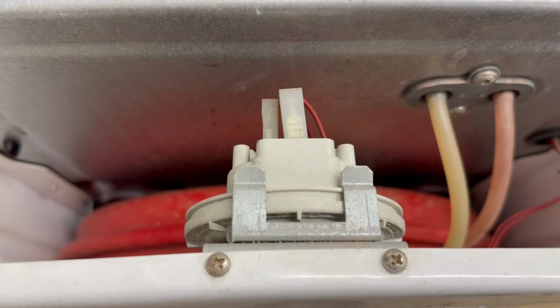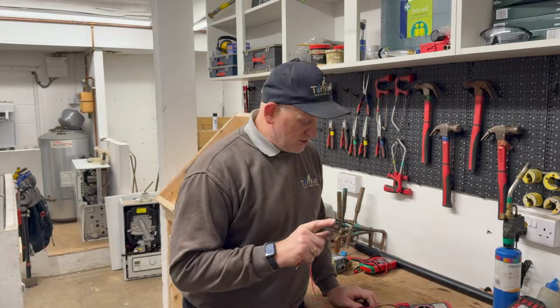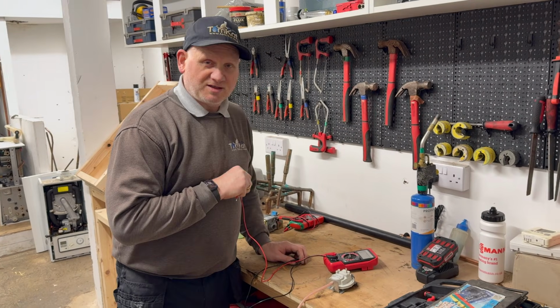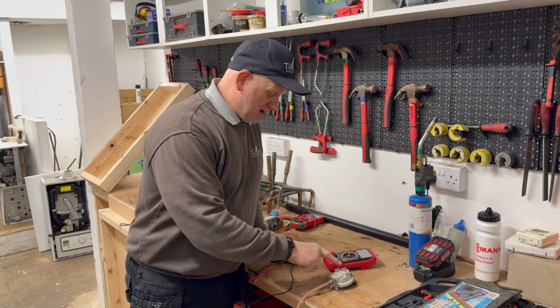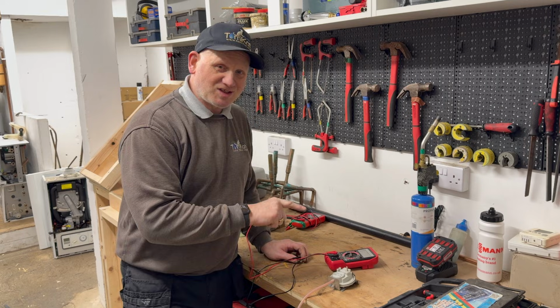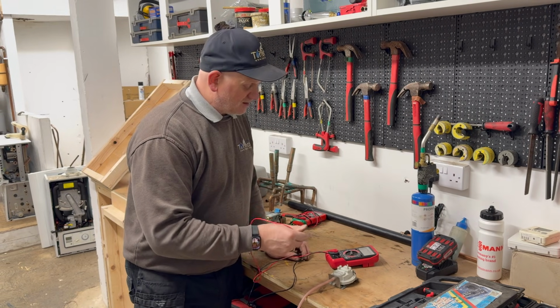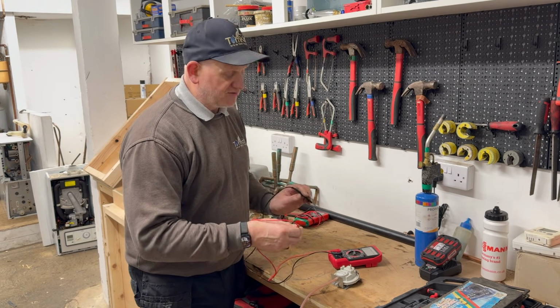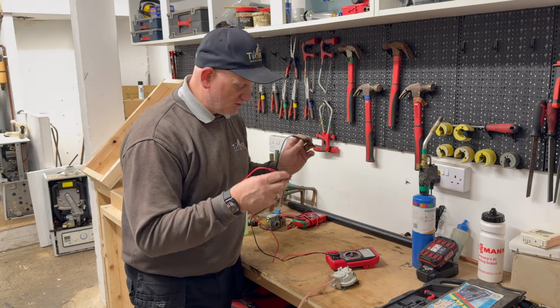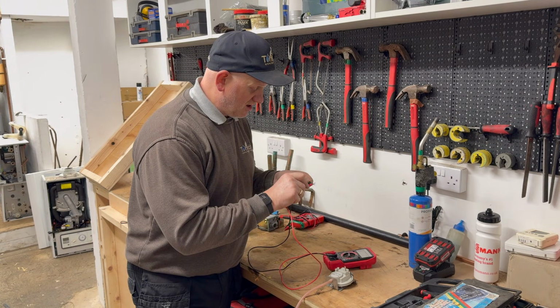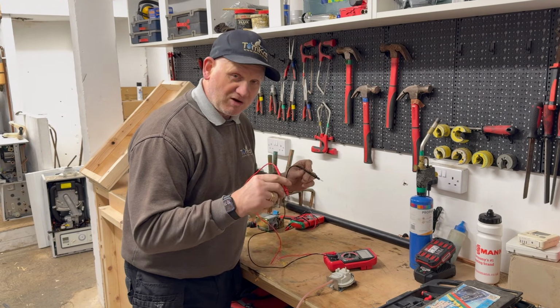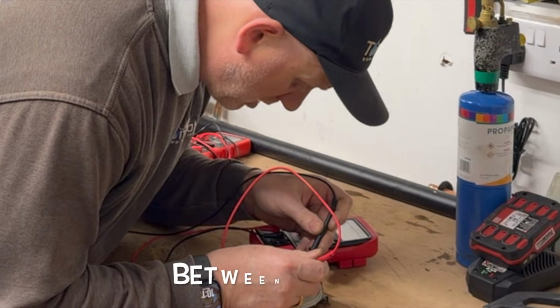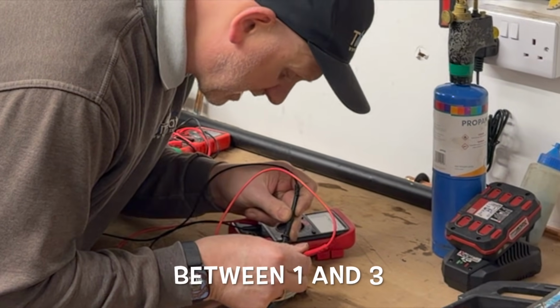Now before we put the boiler on the wall, we might as well check the air pressure switch first. This air pressure switch only has 2 prongs on it. The third one's taken away, so it'll have common and normally open. So if I get my multimeter, put it together on continuity on the buzzer, go onto the 2 prongs, we shouldn't get a buzz.